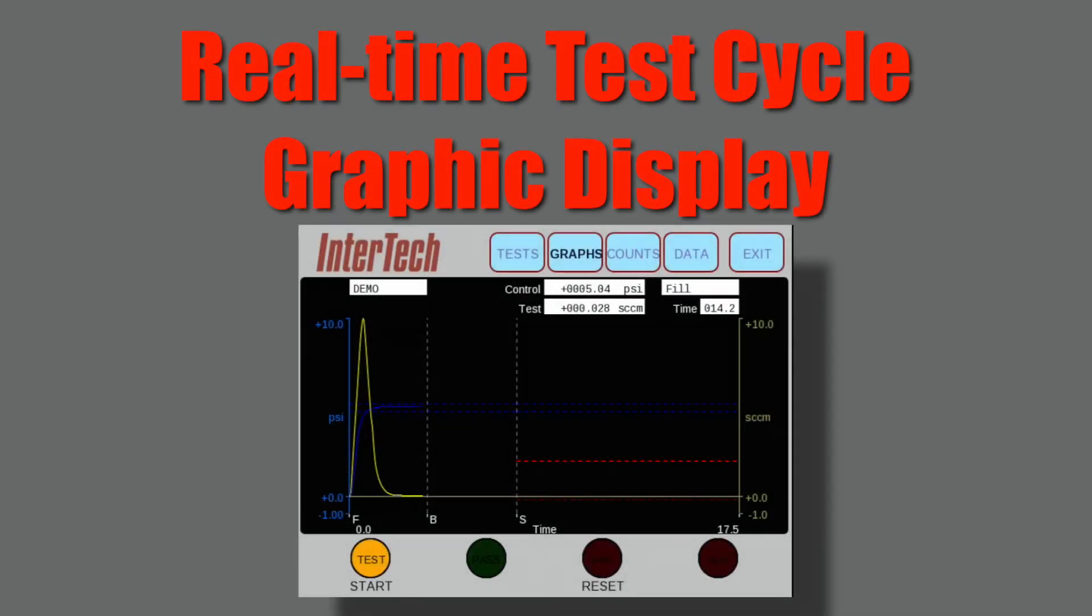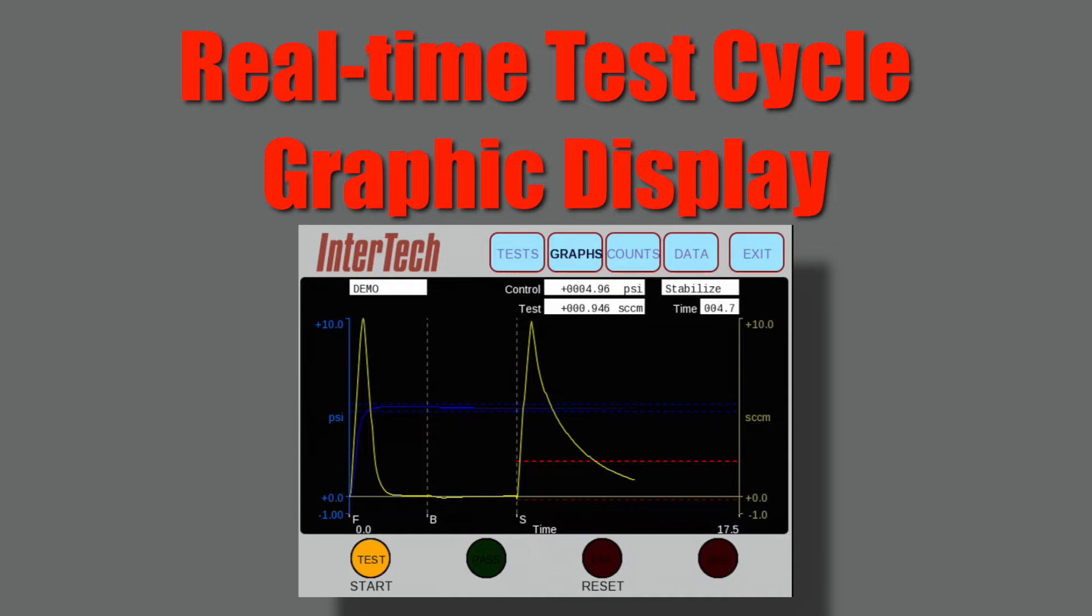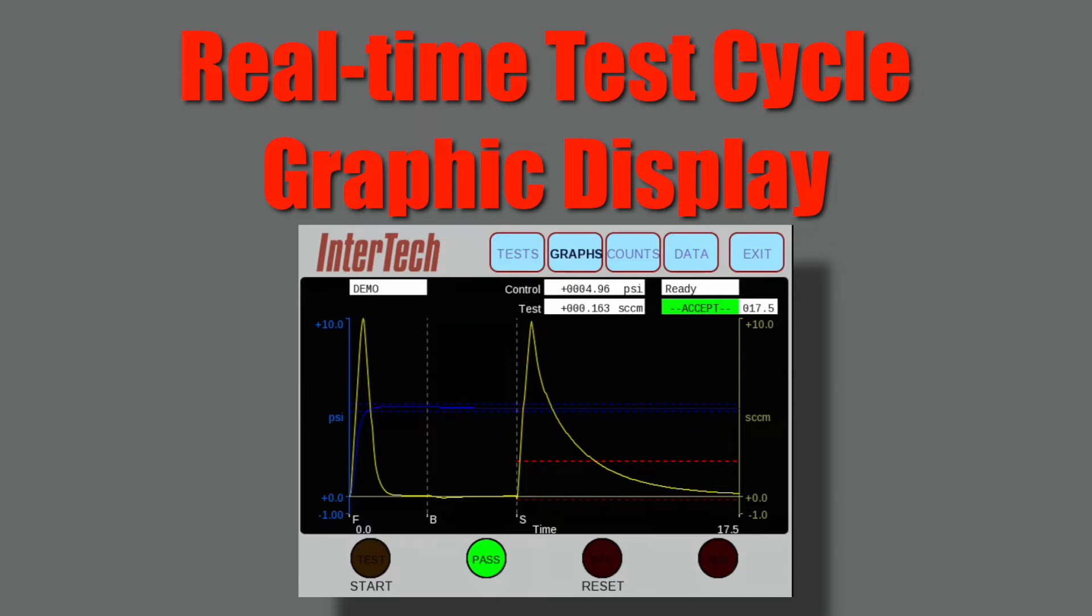Note the unique operation of the high-speed mass flow test and its corresponding test curve. Eliminating the test time required with pressure decay testing saves the user up to 30 percent of leak test cycle time.